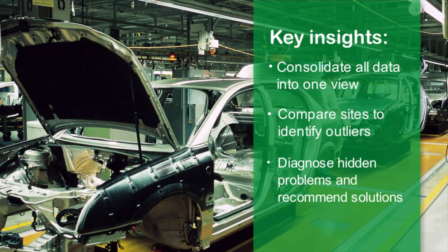The result was an increase in modeled gas consumption, a decrease in gas efficiency performance, and unnecessary gas costs. This surprising decrease in performance led to a deeper review of the monthly energy management survey, which found that this facility did not have thorough shutdown operating procedures. Since then, the client has reviewed their procedures to ensure that energy management is included in the decision making process.